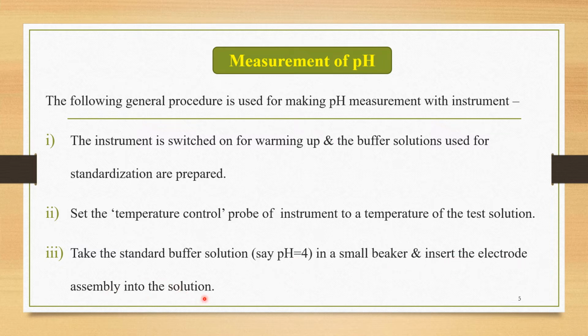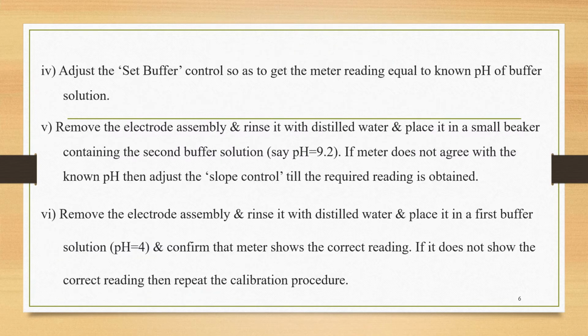Nextly, we have to prepare the standard buffer solution of pH equal to 4. Now, in this buffer solution, we have to insert that particular electrode assembly. So, this is the third step. The next step, step number 4, is to adjust the buffer control so as to get the meter reading equal to the known pH of the buffer solution.